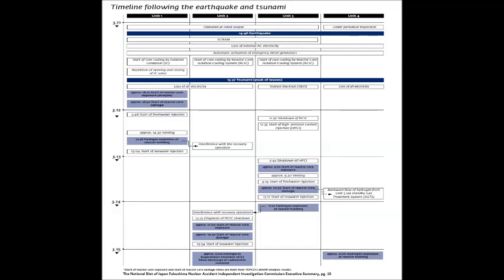At this point, the emergency decay heat removal and makeup water systems previously discussed all shut down, with the exception of the reactor core isolation cooling system for Unit 2, which maintained partial DC power. There were no indications of any reactor plant parameters available in the control rooms. The capability to remotely control motor-operated valves in the isolation condenser, reactor core isolation cooling, and high-pressure coolant injection systems was lost. There was no lighting in the control rooms, with the exception of flashlights.